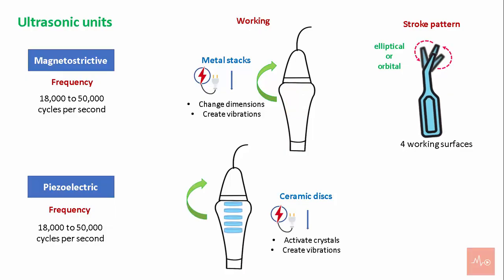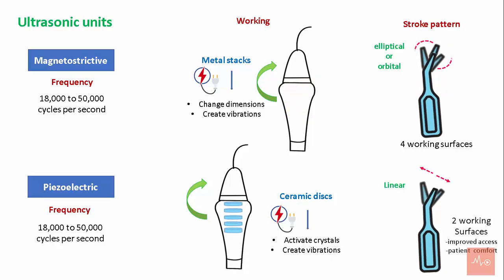Piezoelectric ultrasonic scalers work at a frequency of 18,000 to 50,000 cycles per second. They consist of ceramic discs that change dimensions when electric energy is applied. The tips move in a linear pattern, giving two working surfaces. These tip designs allow improved access in many areas, including furcations, and the slim design with lower power settings improves patient comfort.